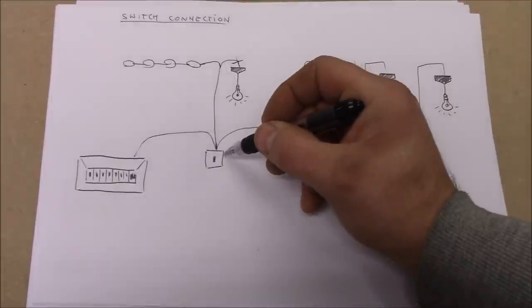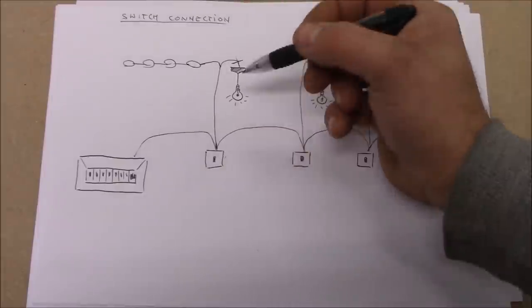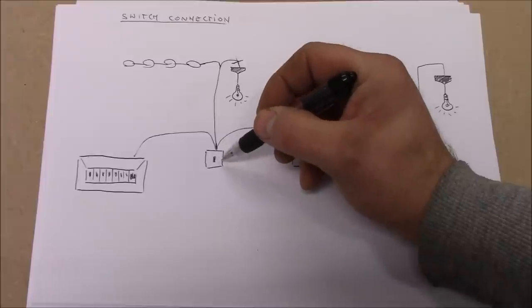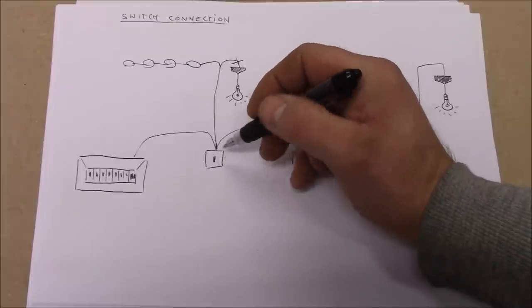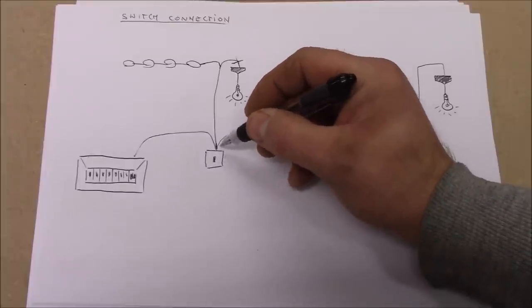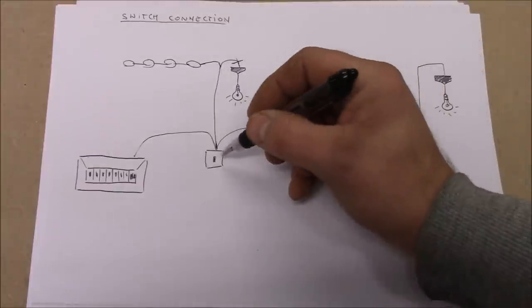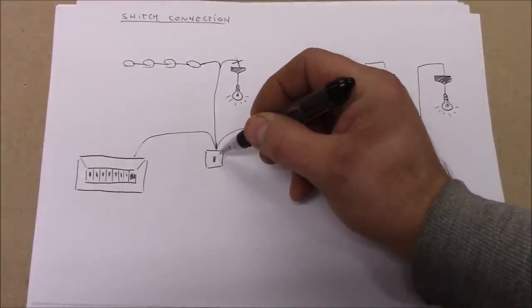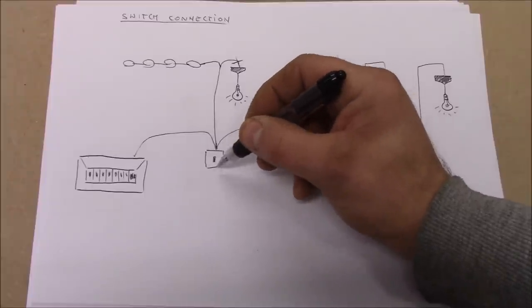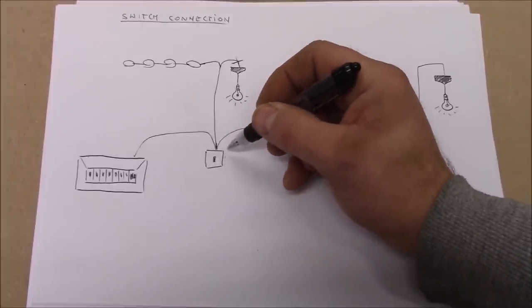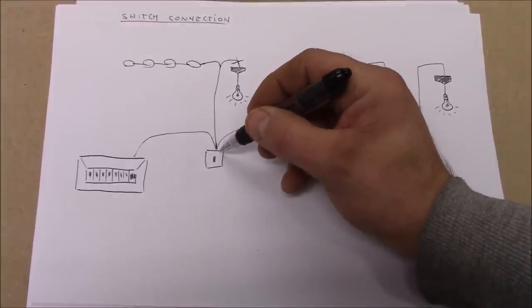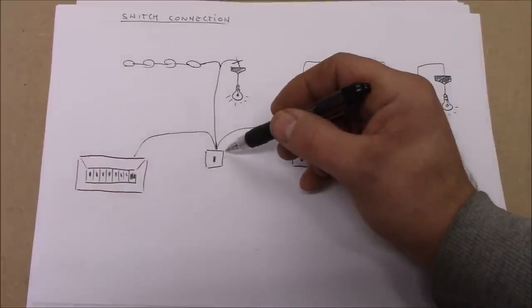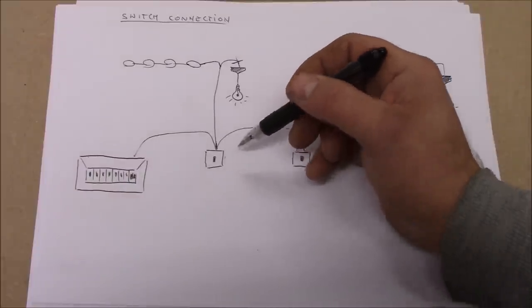At the switch, if we're using a one gang one-way switch, there are just three cables coming in — unless it's a two-gang or two-way switch, in which case there are more. With a one gang one-way switch we've got three cables, so the back box must be deep enough to accommodate them. I recommend using a minimum of 35mm depth for the back box.